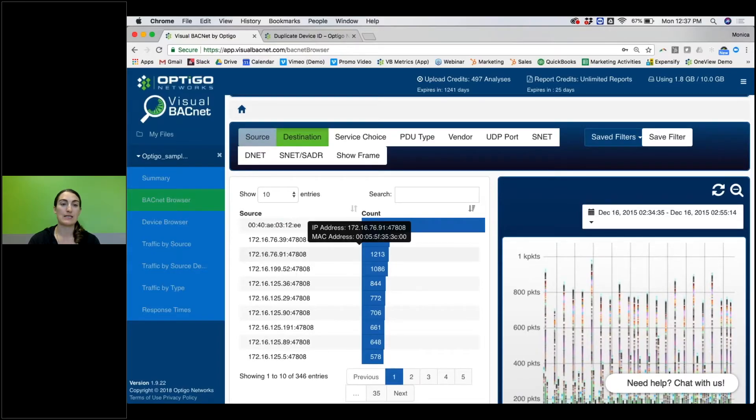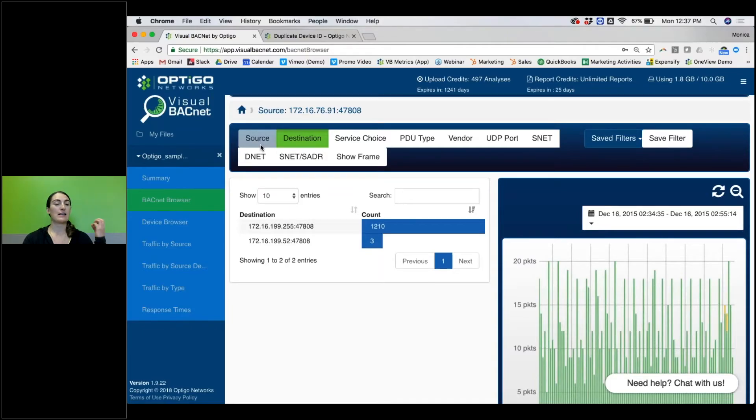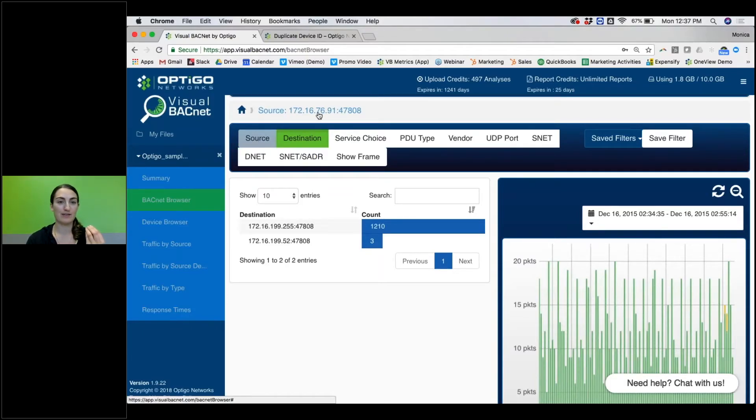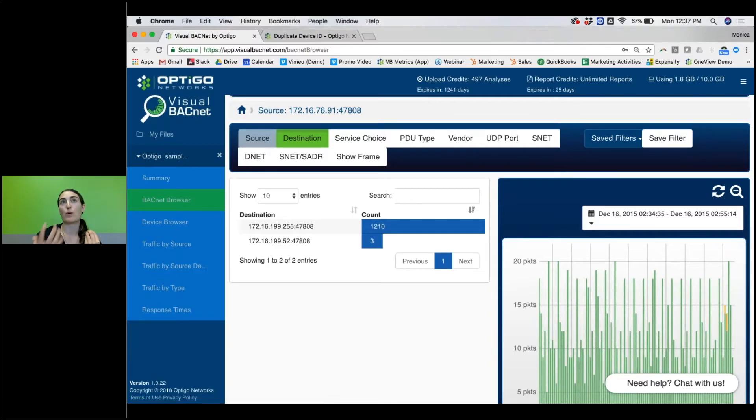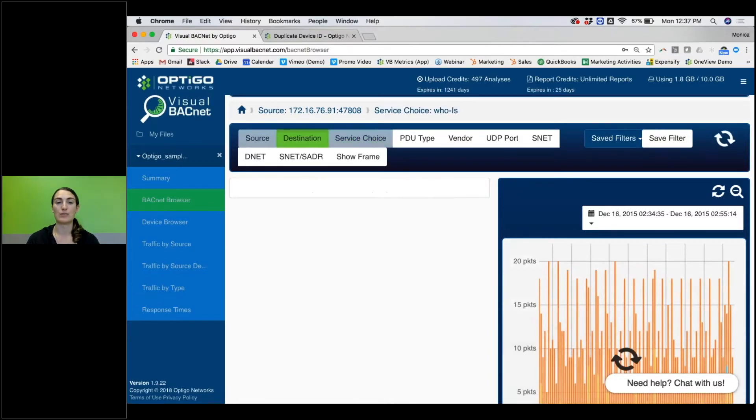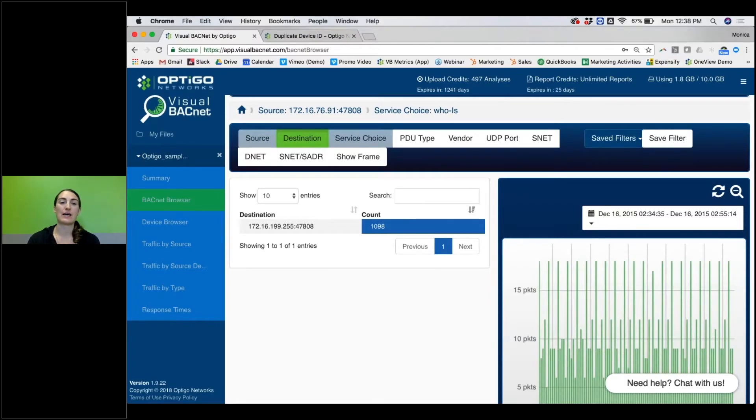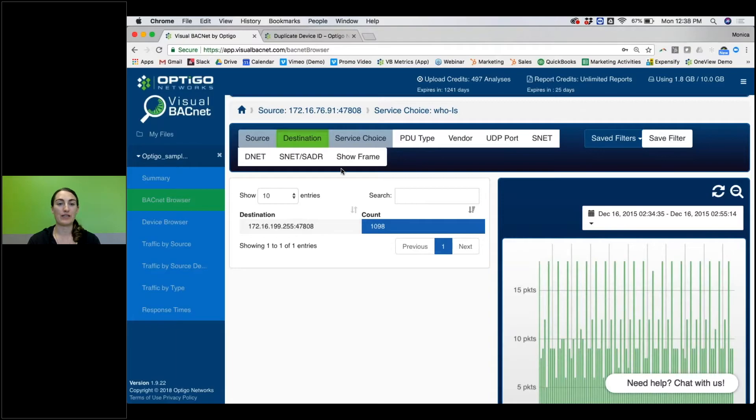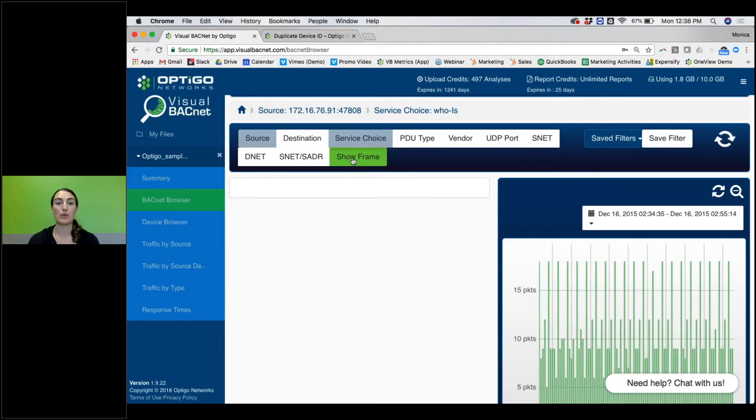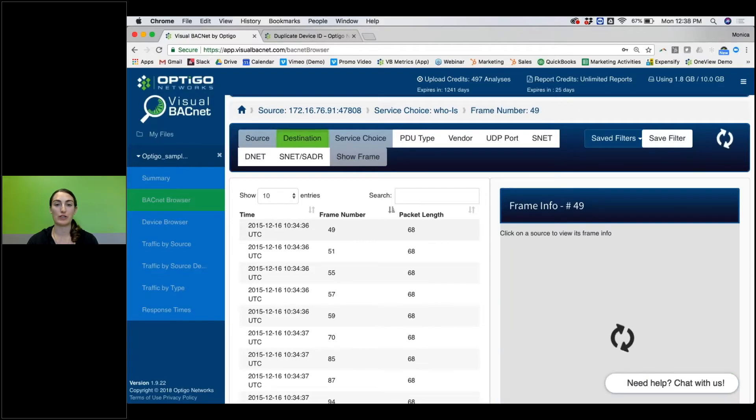I recommend if you have a specific device that's being problematic, come and find it in your source list. It will automatically go to the next button here, but say you want to see source device, this one 76.91, and then you want to see what it's saying. You can look at the PDU type or the service choice. Oh, it's doing a lot of Who-Is. So you can kind of drill down to figure out exactly all the communications from each device. And at any point, if you want to see the actual frame information, you can get into the Wireshark frame.